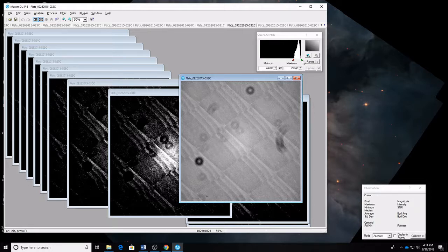The reason that we want these numbers here for the dimmest pixel and the brightest pixel to be within a certain range is because if the image is too dim, then noise that comes from sources like heat and electronic noise start to dominate the image more. So it's like you would be taking a picture of these dim things that you're not interested in, electronic and thermal noise, rather than taking an image of the deviations from average brightness, which is the point of the flat.